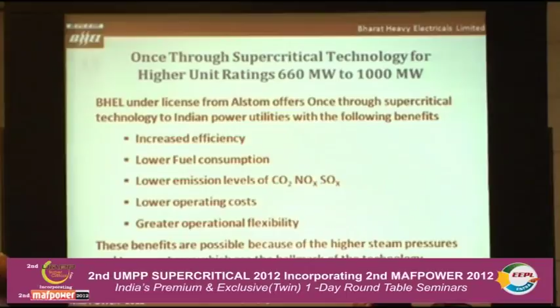And also, when we increase the cycle parameters in supercritical boilers, we also correspondingly increase the temperature, which we will see later. Because of this, we have better efficiency, meaning lower fuel consumption, consequently lesser emission of CO2 and NOx. And of course, operating costs will also come down. Because of this, we are going for higher steam parameters and higher pressures in the higher capacity ratings.